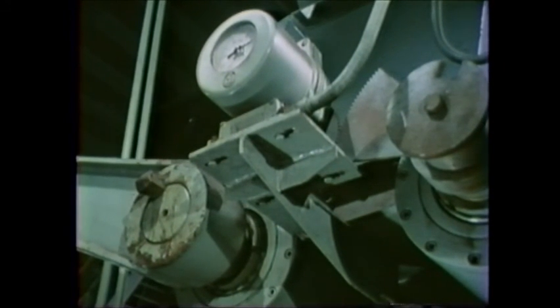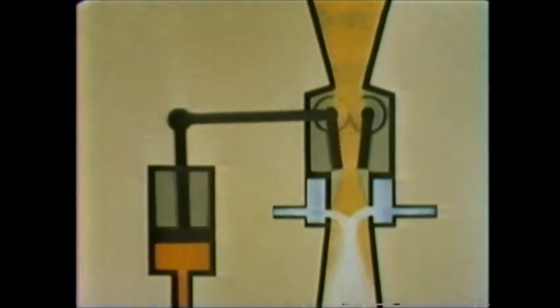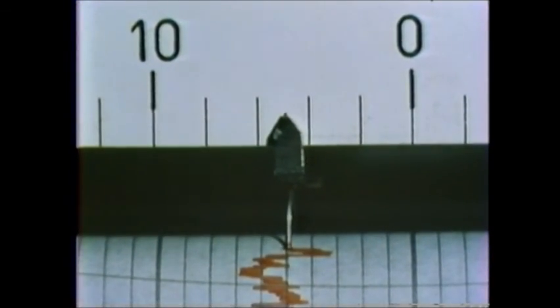The venturi has a movable throat, the opening of which is automatically adjusted to accommodate the fluctuating volume of the passing gas. The movable throat keeps constant gas velocity through it. At the same time, it adjusts the pressure inside the hood. This enables the OG process to operate with stability and efficiency throughout blowing.